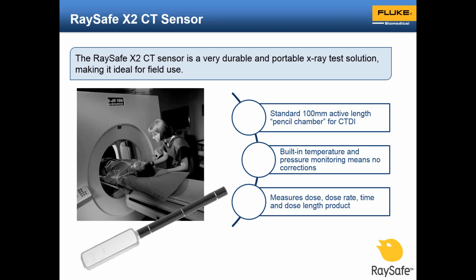Since the sensor has built-in bias supply and electrometer, there is no need for the fragile and noisy analog cables traditionally associated with ion chambers. The sensor also automatically measures and corrects for temperature and pressure, so you get an accurate reading every time without having to think about the environment you're working in. Another unique feature of the X2 CT sensor is the ability to measure exposure time and dose rate waveforms. These features come in handy to ensure the sensor has been placed at isocenter and to determine the starting point of the tube with each CT scan. The X2 CT sensor measures dose, dose rate, time, and dose length product.